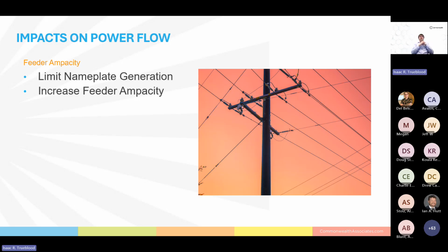So, what are some ways to mitigate this? The first and easiest way is to limit the distributed energy resource's nameplate. If you limit a distributed energy resource's generation to within the allowable feeder ampacity, there will be fewer issues. But I want to stress, a review of the feeder's ampacity between the distributed energy resource and the feeder is still needed to determine the limit before upgrades are required, or what upgrades are required if a specific nameplate is desired. However, such a review will ensure current equipment is capable of handling the power flow and prevent damage to the distribution system. This will also highlight the limiting factors on the feeder's ampacity, and sometimes an upgrade is a long time coming.